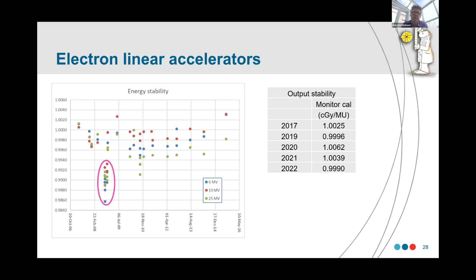So this is a measure of the collateral I talked about, that a source is a source, and you know exactly what it is, and you know what the decay means for its activity, whereas for an electrically generated device, you've got to worry about the stability of the energy and the stability of the output. So this is looking over the last sort of 5 years of the stability of our absolute output of the accelerator. And, you know, it's not bad, but it's certainly not 0.1%, and it's definitely not 0.5%, which is what we saw with kV X-rays, and is routinely possible even with a simple radioactive source. So it can give you some level of repeatability, but it is not what we want.